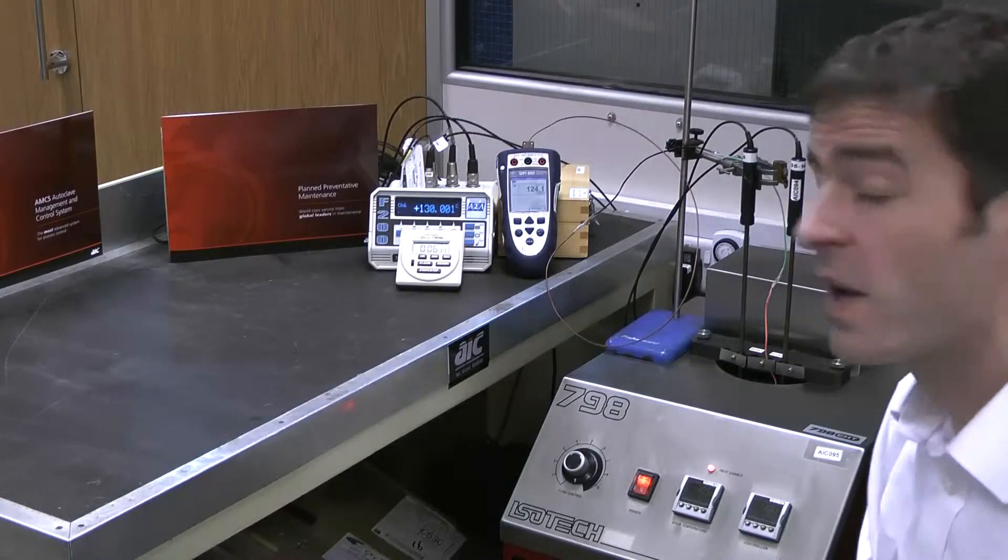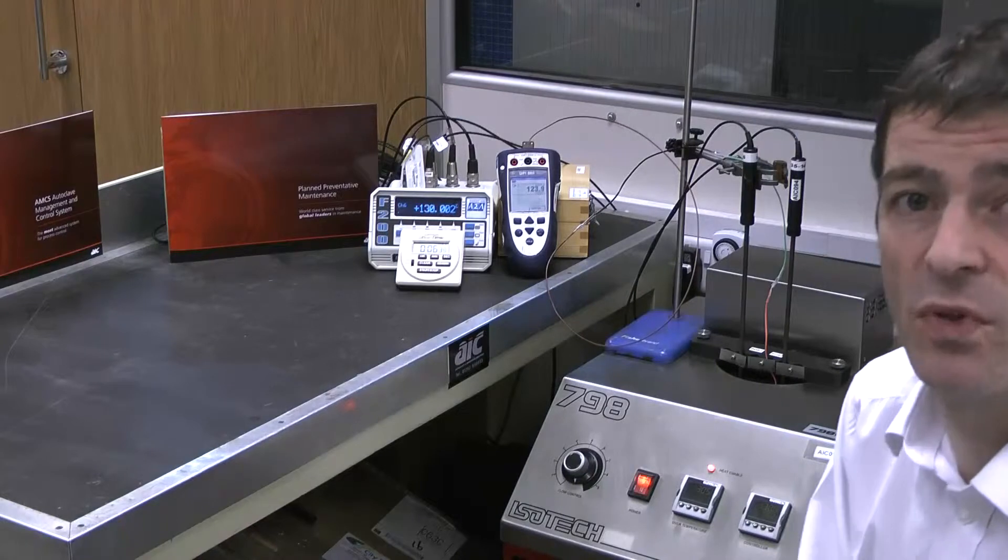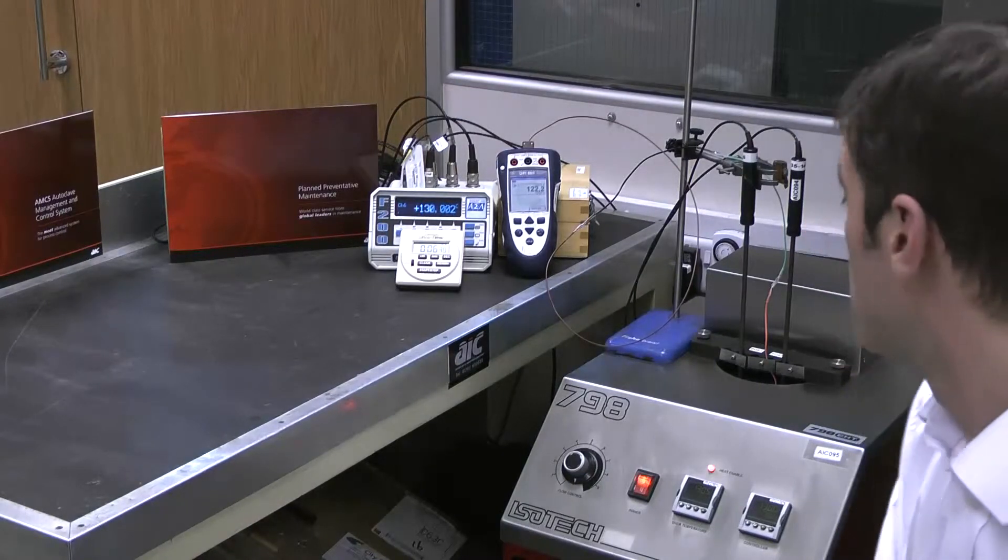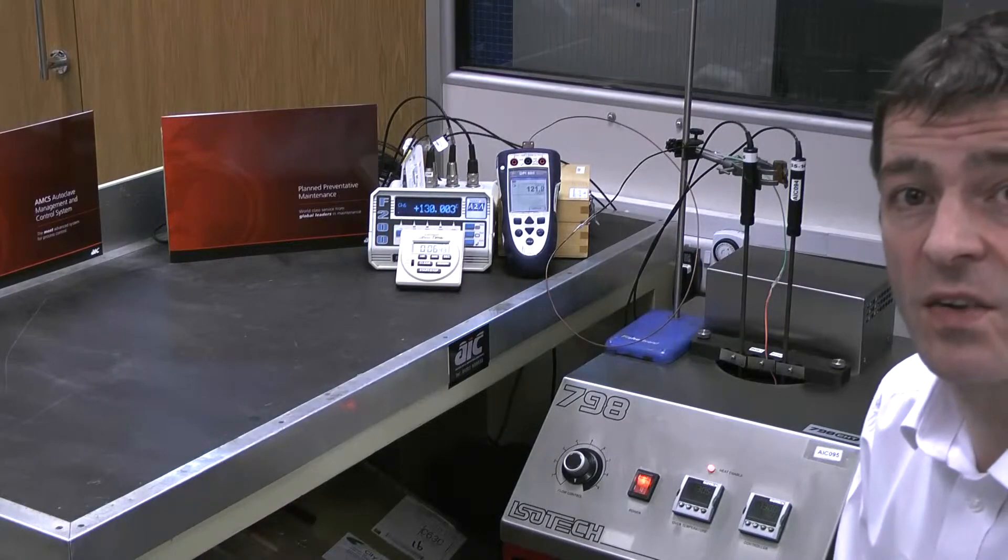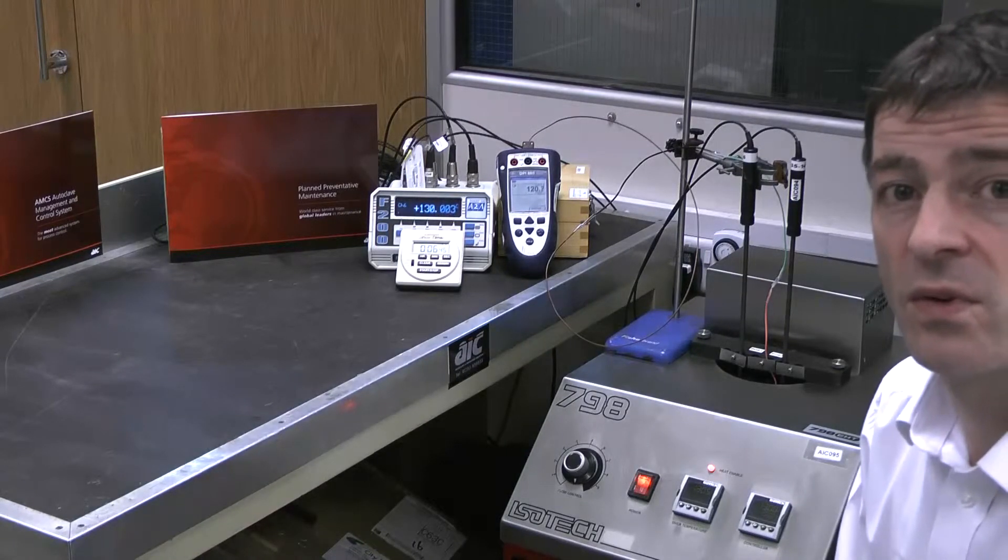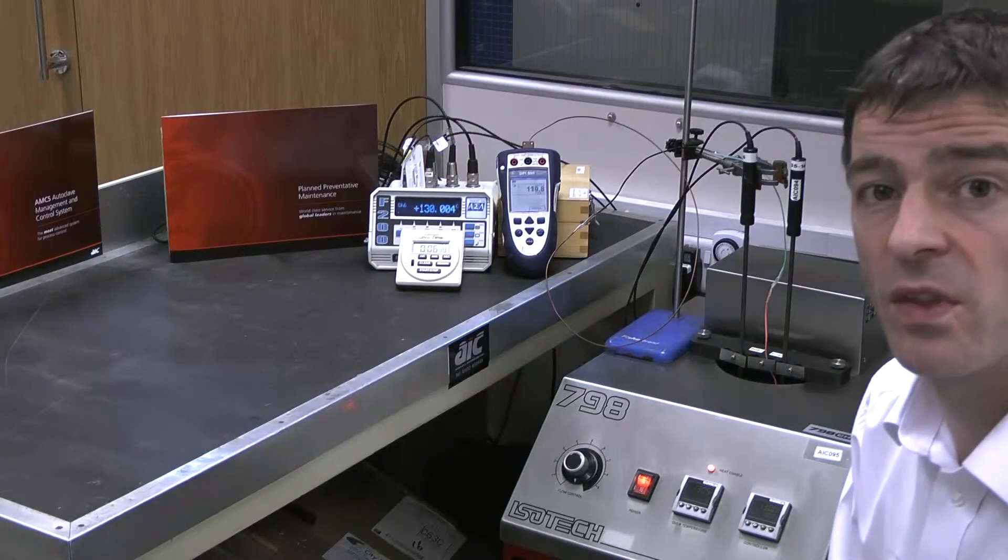because our calibrator thinks it's Type K, we've introduced a significant error in the character of the cable again, more than you would experience in real life, of course. And you can see the reading is already starting to go into error. So, we'll start the timer again, give it five minutes, and see what happens to the reading.